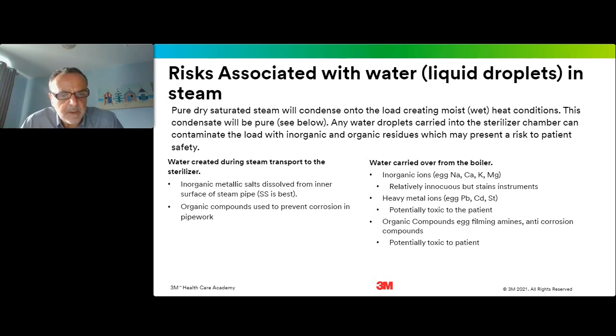So you might have inorganic ions such as sodium, calcium, potassium and magnesium, not eggs, that should be EG. These are relatively innocuous, but they might leave deposits or stain instruments. We can have heavy metal ions such as lead, cadmium, strontium, which of course are then potentially toxic to the patient if they end up on the surface of our instruments. And then we can have organic compounds such as filming amines or anti-corrosion compounds, and these again could be potentially toxic to the patient.